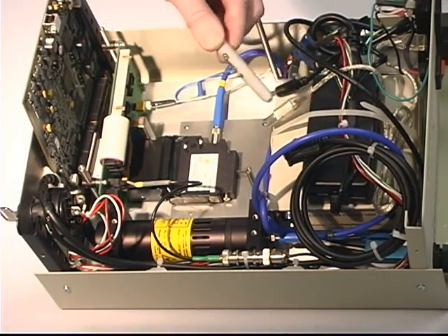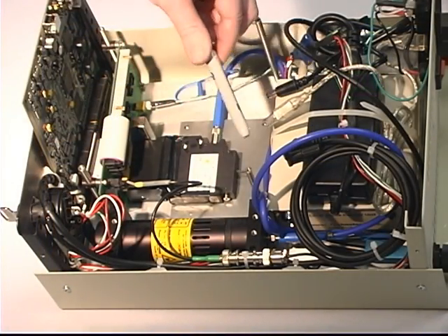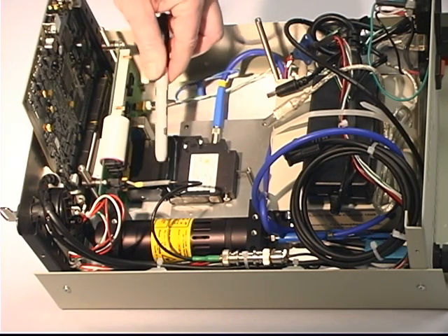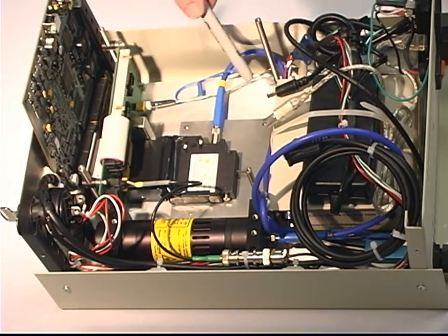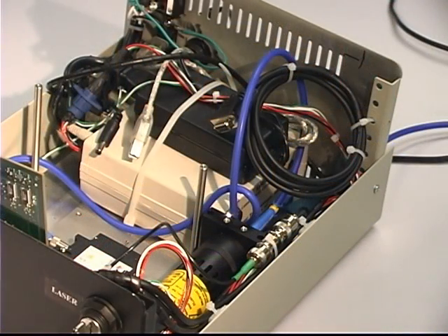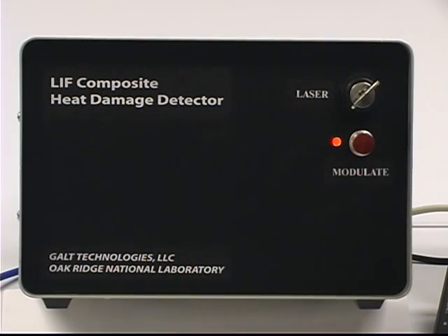The LIF unit is comprised of a diode laser excitation source, a spectrometer, a 32-channel linear array photomultiplier tube, and detector electronics, an analog-to-digital converter, laser power supply, main power supply, and reflection probe. The front panel of the LIF unit was designed to have minimal input from the end user. A key switch is used to activate the diode laser power supply, while a push-button switch is used to activate the software-controlled modulated output of the laser. An LED indicator is used to alert the user that the laser output is activated.